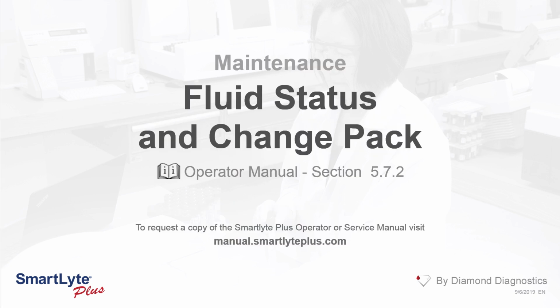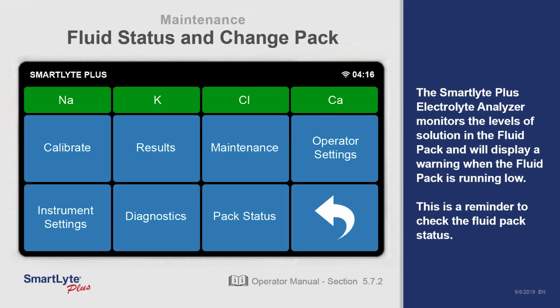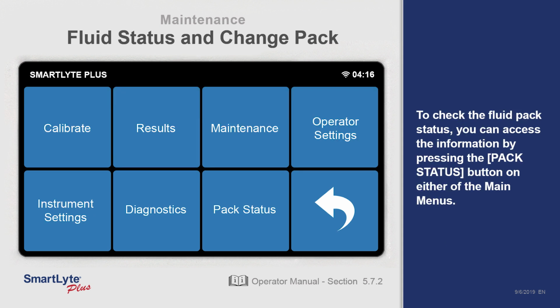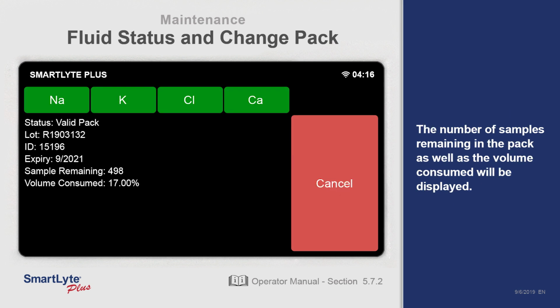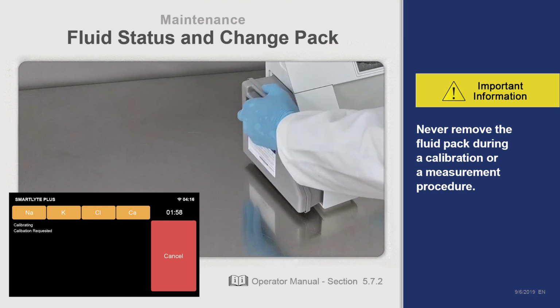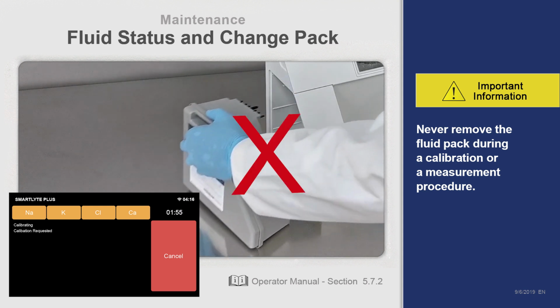Checking the fluid pack status and changing the pack. The SmartLyte Plus electrolyte analyzer monitors the levels of solution in the fluid pack and will display a warning when the fluid pack is running low. This is a reminder to check the fluid pack status. To check the fluid pack status, you can access the information by pressing the Pack Status button on either of the main menus. The number of samples remaining in the pack as well as the volume consumed will be displayed. Never remove the fluid pack during a calibration or measurement procedure.